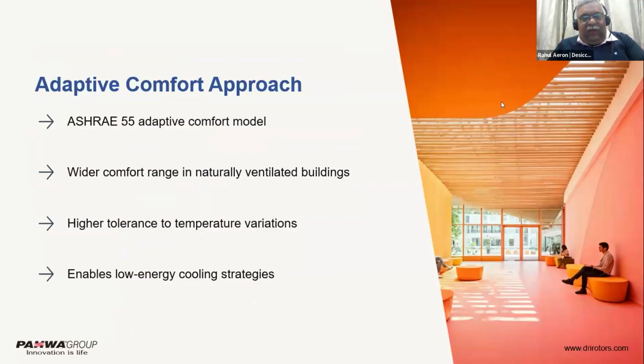I would like to focus on what we call an adaptive comfort approach. Gone are the days when we were talking about thermal comfort as maintaining 22 degrees centigrade in our spaces. Even our room air conditioners now start at 24 degrees centigrade. For HVAC engineers, there is a standard, the ASHRAE 55 standard, which gives an adaptive comfort model. What that model means is that when you have higher mean prevailing outdoor air temperatures, like in India, where temperatures can go as high as 48 degrees centigrade, a person can feel comfortable at 30 or 32 degrees centigrade with the right amount of air velocity and humidity.